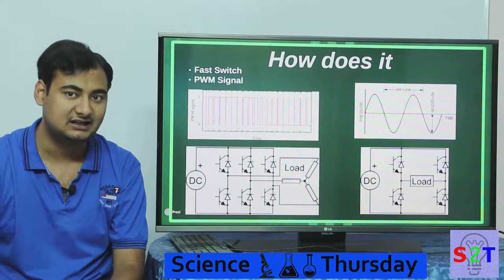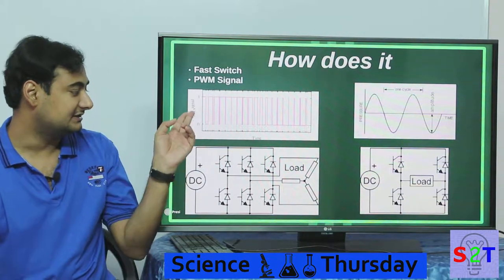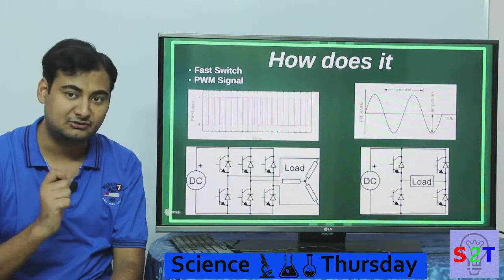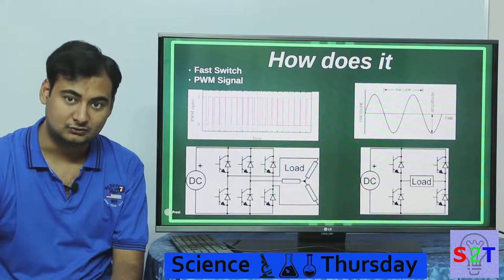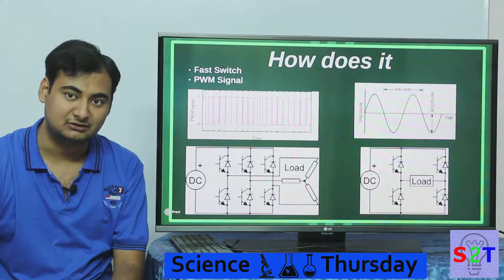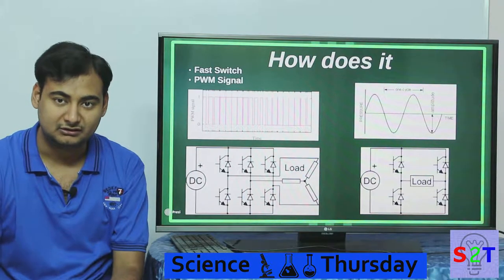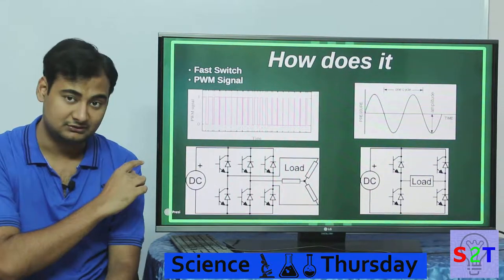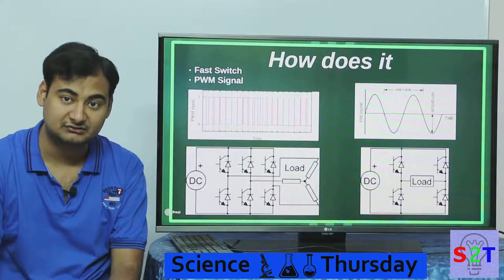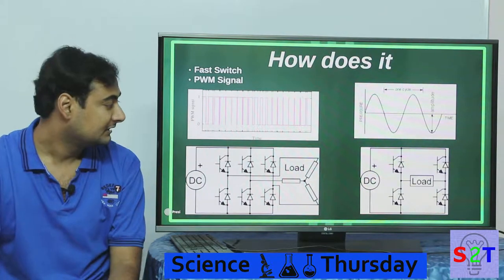This is how we ended up creating a sine wave inverter. What we did is all these switches - we are turning them on and off much more than is needed in older designs, which you can call square wave. What we used to do is only do on and off 60 times a second to make 60 Hertz mains power. This, however, because of advances in fast silicon electronics or solid state IGBTs, we can do that thousands of times a second.